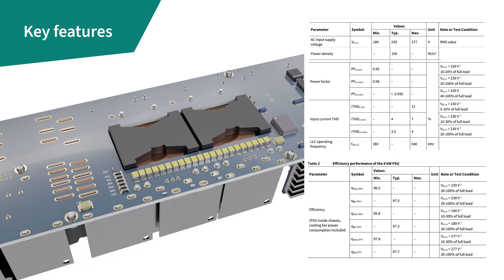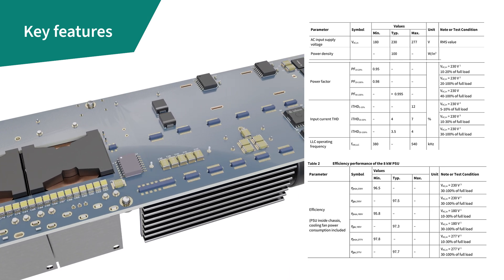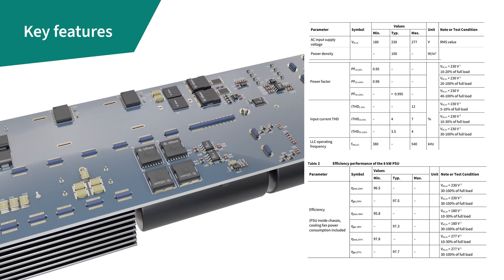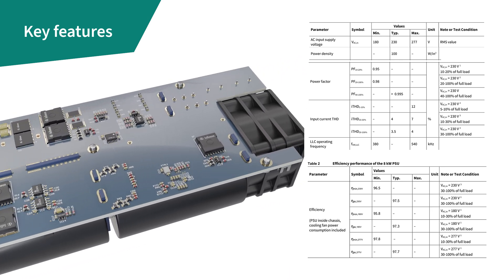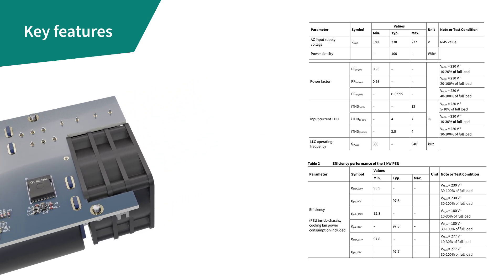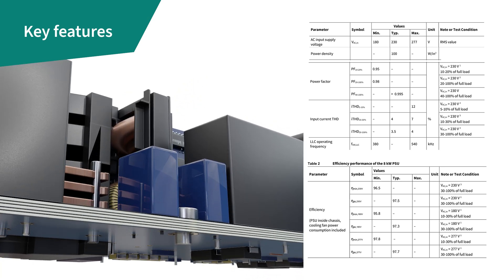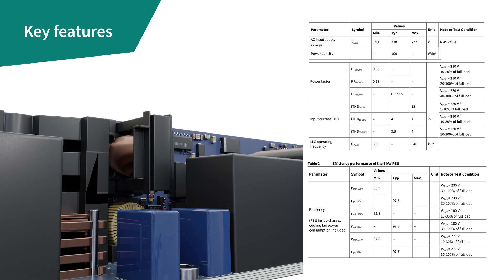It is capable of peak efficiency of 97.5% and full load efficiency of 96.5% at 230 volts AC input. The AC input voltage range is 180 to 277 volts.